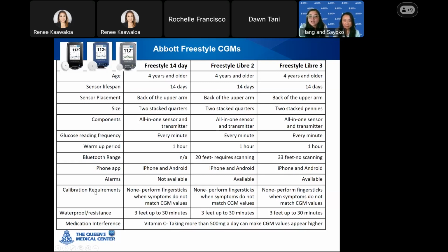For calibration, there are no requirements. However, it's recommended to perform finger sticks when symptoms do not match the CGM values. The waterproof resistance for all is also 3 feet for up to 30 minutes. And medication interferences can include vitamin C if you take more than 500 milligrams a day. That can make your values appear higher.